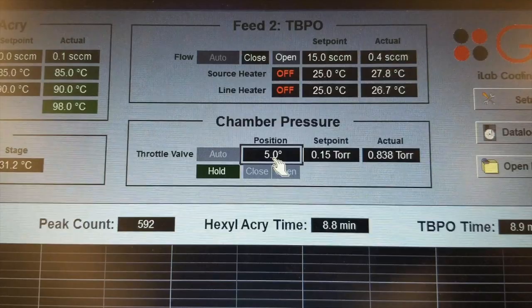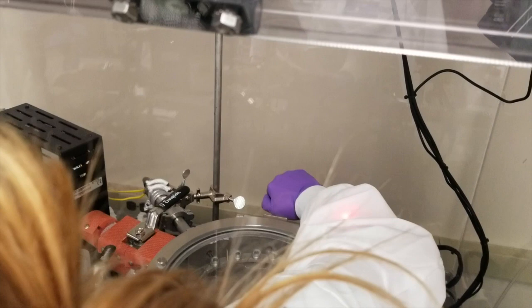We then open up valve 2 fully and wait for the pressure to drop below 1000 millitorr and then open valve 1 through the computer. Afterwards we open up the nitrogen gas valve as little as possible while trying to achieve a stable chamber pressure of 0.150 torr.